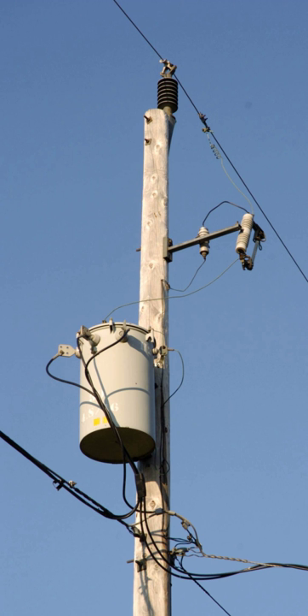Topic: applications. In North America, individual residences and small commercial buildings with services up to about 100 kVA, 417 amperes at 240 volts, will usually have three-wire single-phase distribution, especially in rural areas where motor loads are small and uncommon.